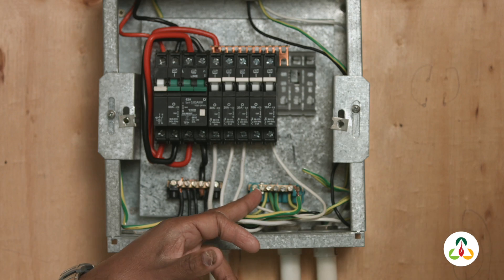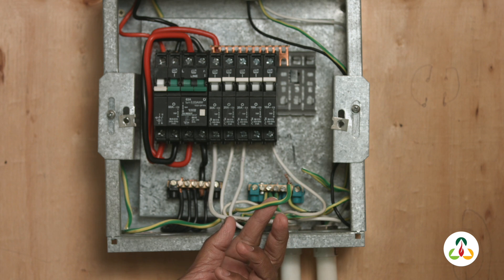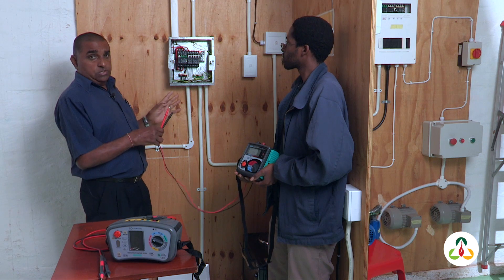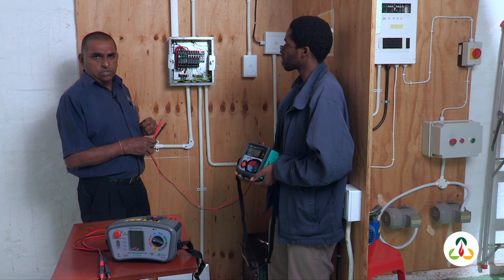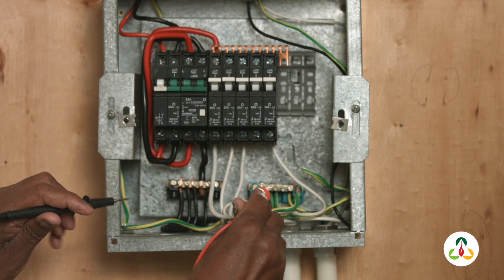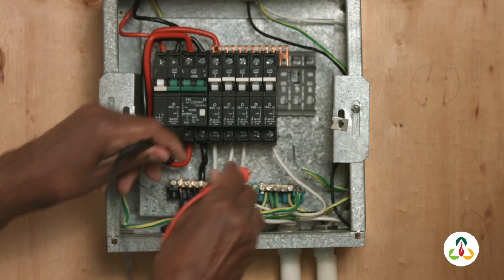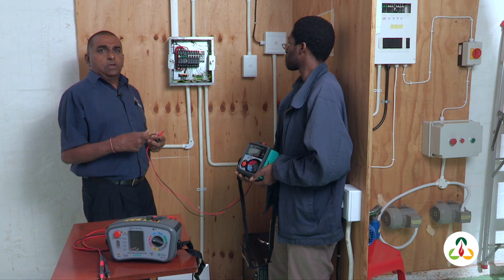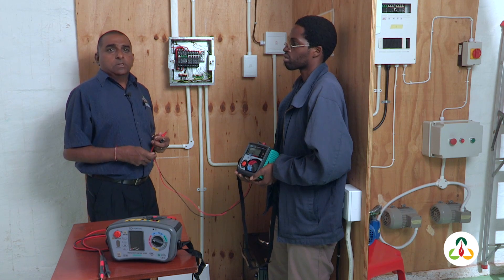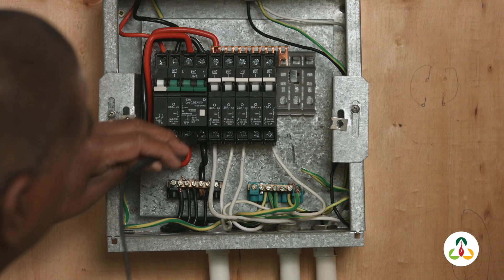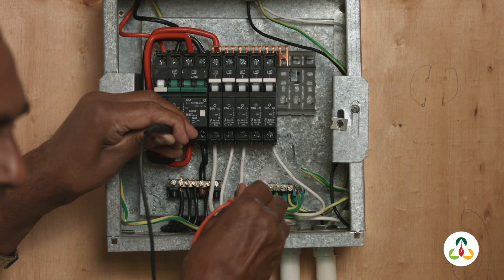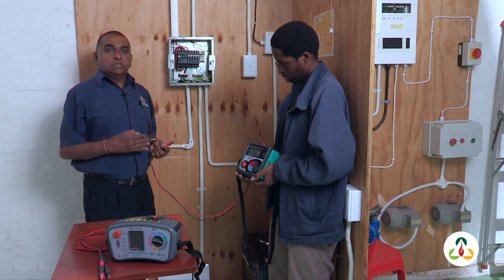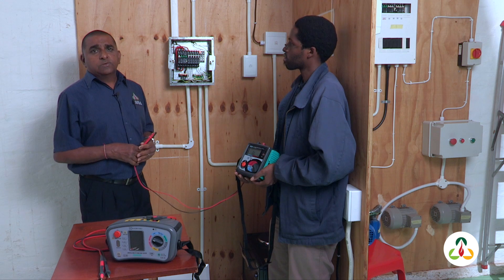Our main earth bar is indicated at the bottom here. You would have noticed that the main supply earth has been removed, as I want to test the insulation between my installation and the conductors. Testing between the live and the earth at the earth bar, my meter reading is still OL — infinity — indicating an insulation resistance higher than one mega ohm. I then test between the neutral and the earth, and once again the meter shows OL, confirming the reading is above one mega ohm. That completes the insulation resistance test.